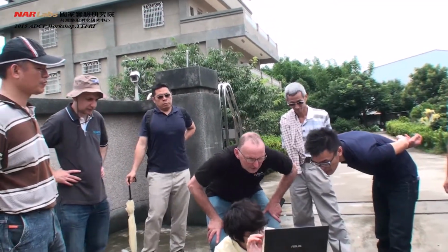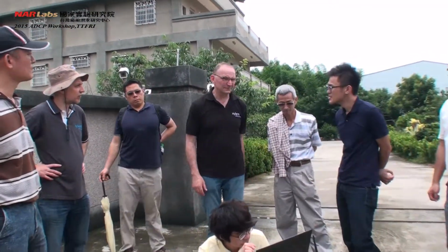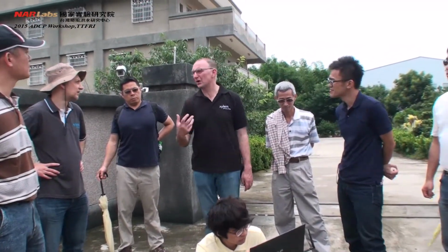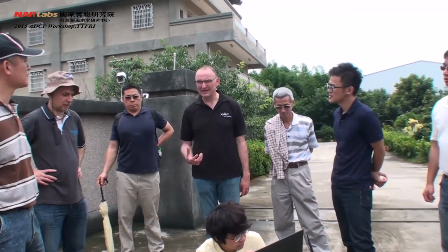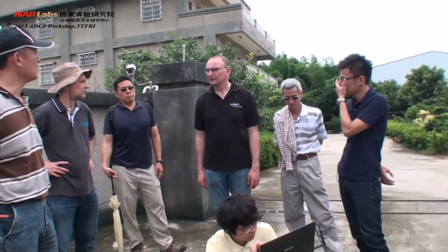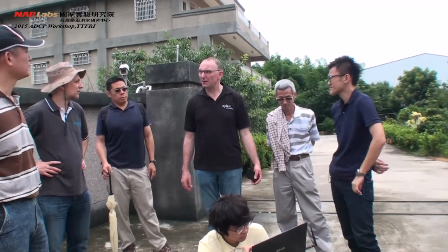The next one, smart pulse enabled or disabled. If we disable it, the instrument will work in pulse incoherent only. So if you're having a lot of problems and the data's looking not so good, it might be worth turning smart pulse off.